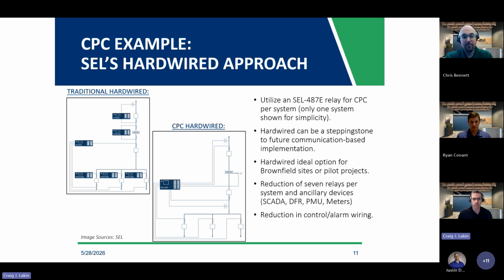And then we're also talking about the reduction in the ancillary devices. That would be all the SCADA functions, the digital fault recording, digital monitoring equipment, phasor measurement units, metering functions, and also the smaller miscellaneous wiring associated devices, such as test blocks, fuses, control switches, etc. Lots of reduction in equipment by doing this kind of centralized protection. And all this results in a significant reduction in control and alarm wiring. So as you can see here, we're not changing any of the functionality. We're just wiring the CTs and VTs to a centralized box and programming it with the same functions that the other boxes would have done. So that's a good stepping stone project.